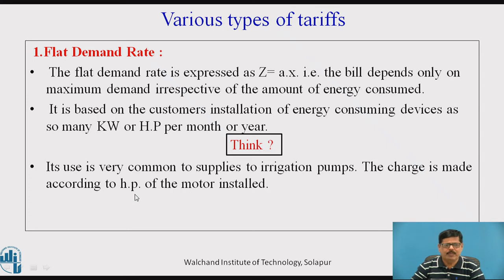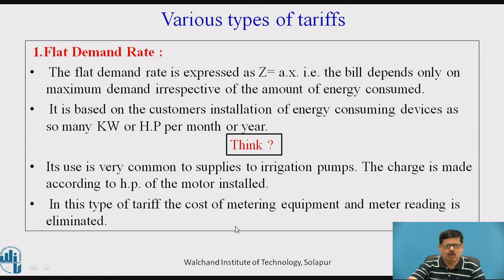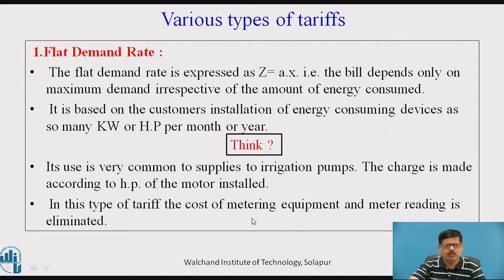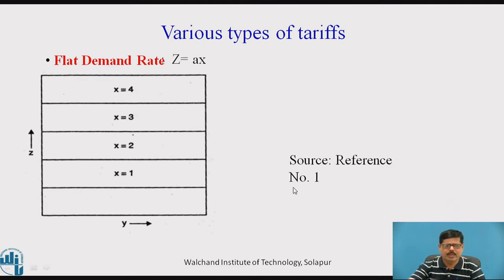That is how the flat demand rate is charged. In this type of tariff, the cost of metering equipment and meter reading is eliminated, since we are charging only upon the installed capacity — there is no need to record a meter reading or install a meter. Graphically, Z = A × X shows that the tariff Z depends only on maximum demand X and remains constant irrespective of the electrical energy used (Y). This is the flat demand rate.